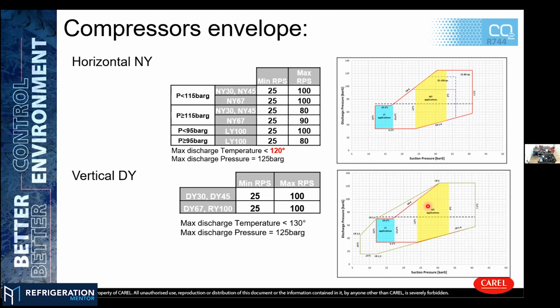both for the vertical or for the horizontal one. I noticed that the maximum discharge temperature is a little different on the horizontal one than the vertical one. Do you know what the reason is for that? Yeah, basically by the limitation of the mechanics, the vertical one is a little bit more robust than the horizontal one. So we accept a little bit higher temperature and a wider range of the application. But it's a 10 degree difference between one and the other. It's still way too hot. Either one of them, 120 Celsius or 130 Celsius, is still too hot. You're running hot there.